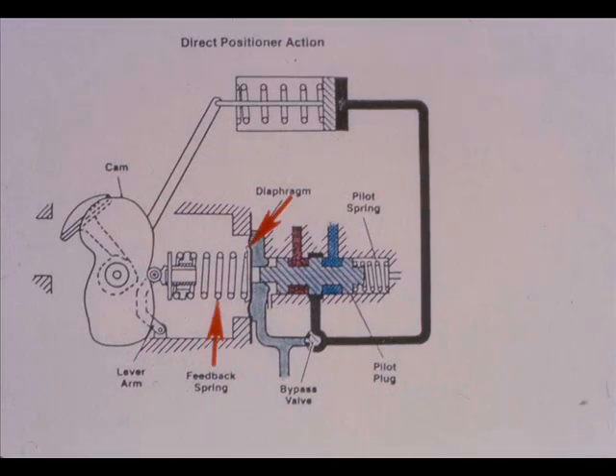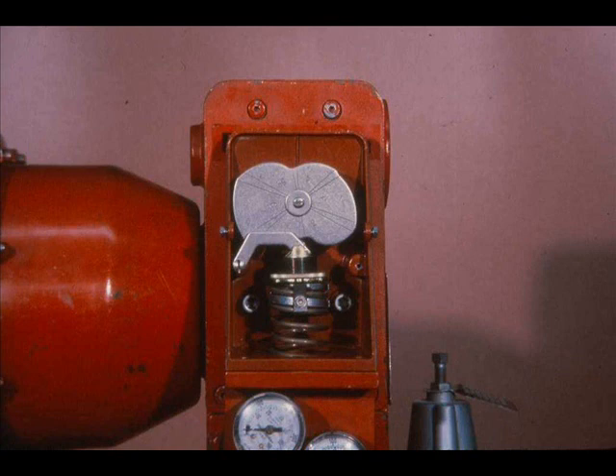The valve plug continues to move until the feedback spring force balances the force of the instrument signal on the diaphragm. In the new balanced state, the valve plug is positioned in a programmed relationship to the instrument signal, governed by the cam. The cam is the intermediate element in the feedback mechanism between the actuator and the feedback spring. Its profile determines the relationship between valve plug position and the control signal, providing linear, split range, or equal percentage control characteristics.